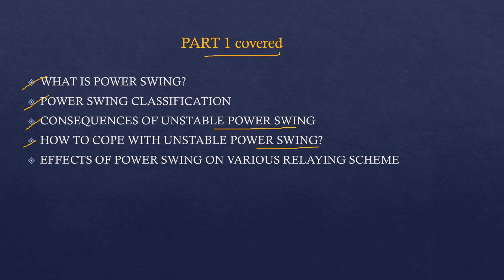Also, here we have mentioned the out-of-step protection technique which prevents tripping in case of stable power swing. In a stable power swing, the rotor has achieved the new angular position and therefore tripping of the generator is not desired.